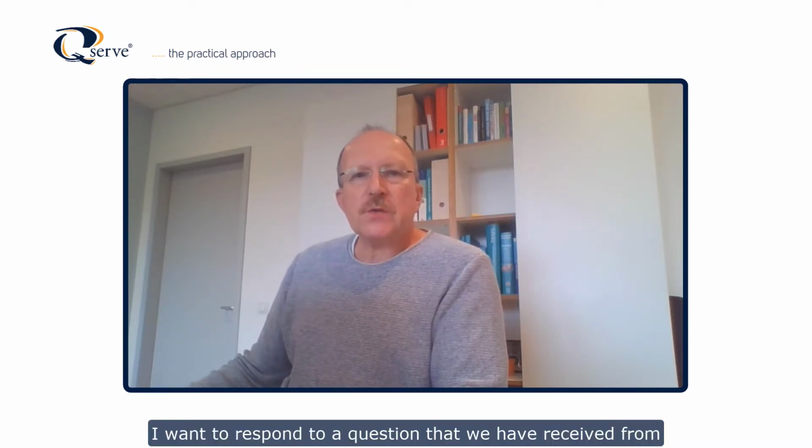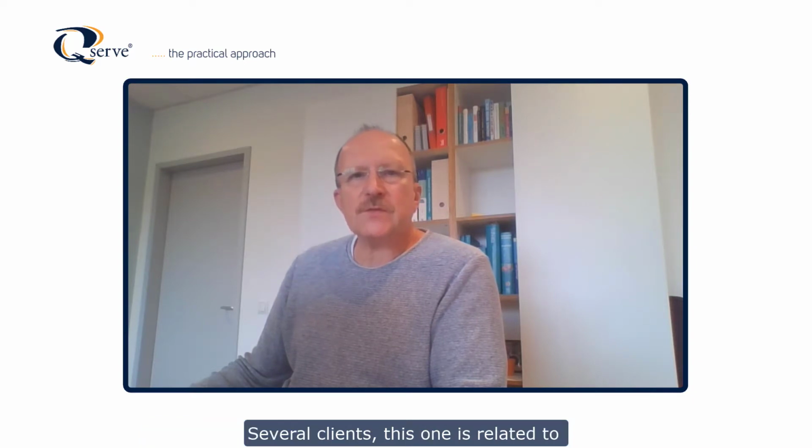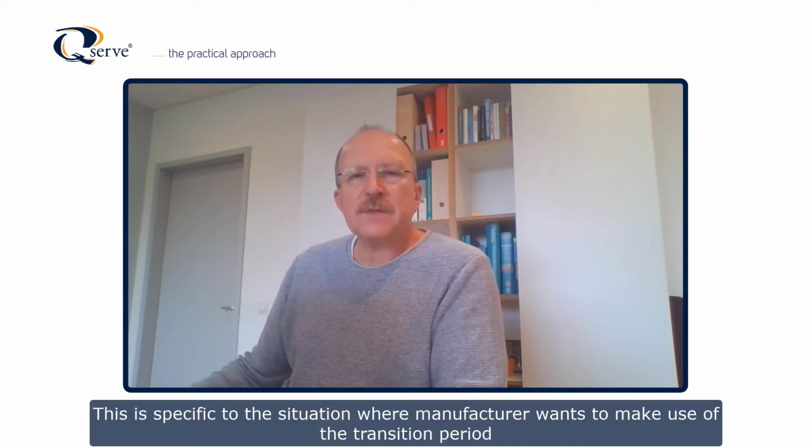I want to respond to a question that we have received from several clients. This one is related to the reissuing of a MDD Declaration of Conformity after having implemented changes to the product. This is specific to the situation where a manufacturer wants to make use of the transition period that MDR Article 120 allows.